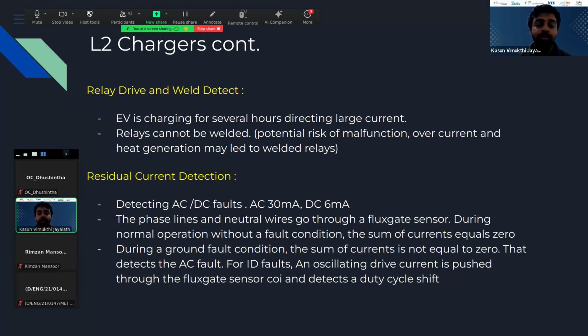The phase and neutral wires go through a sort of fluxgate sensor. During normal operation without any fault current, the sum of all the currents is 0, as we know from our theorems. If it's not 0, and it detects 6 milliampere for DC or 30 milliampere for AC, the charging should stop. During a fault condition, the sum of current is not equal to 0, which detects the fault.